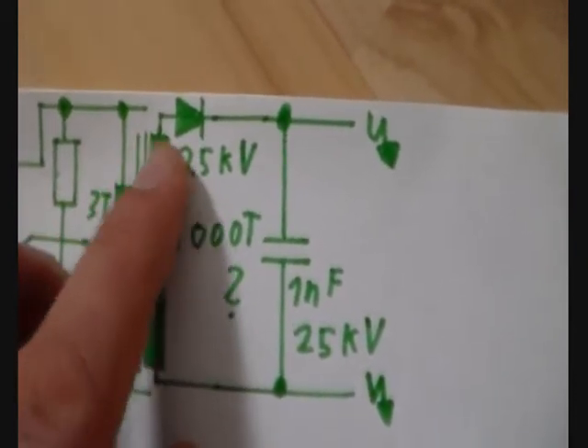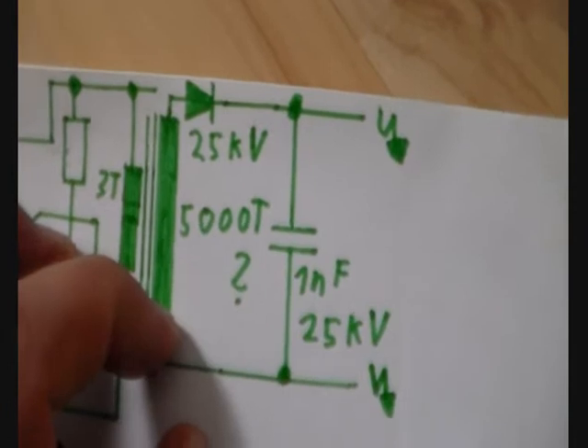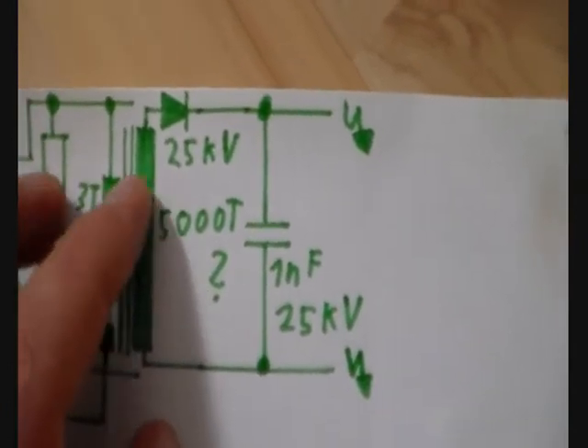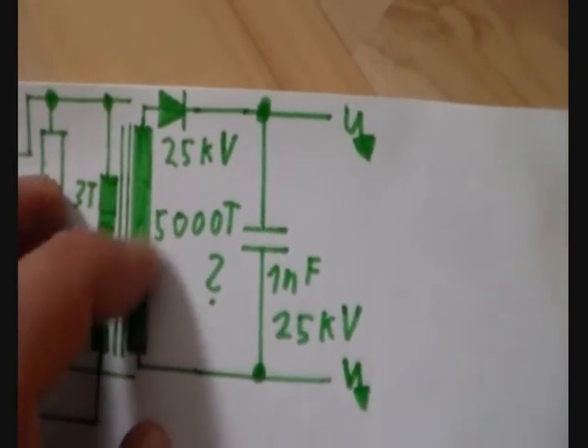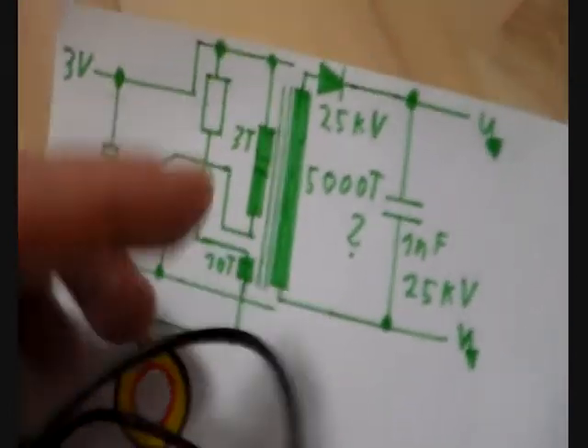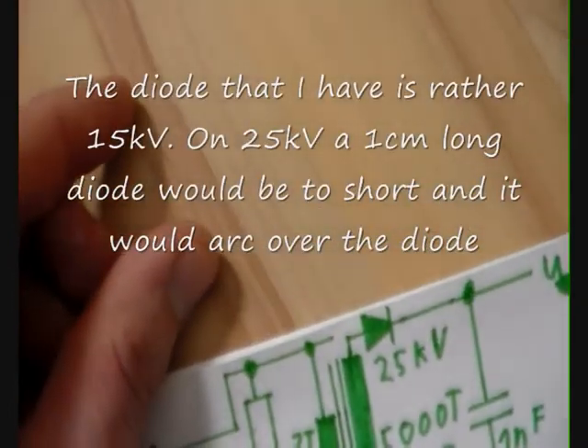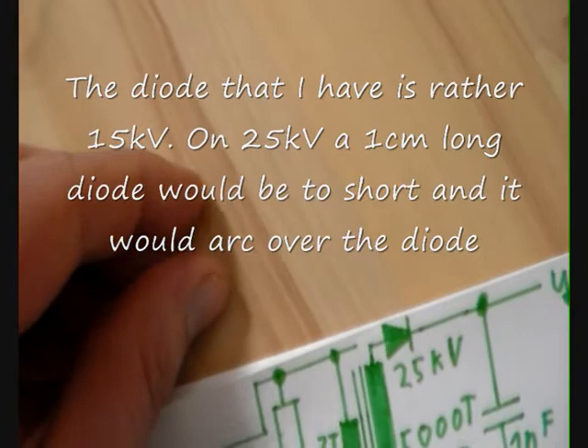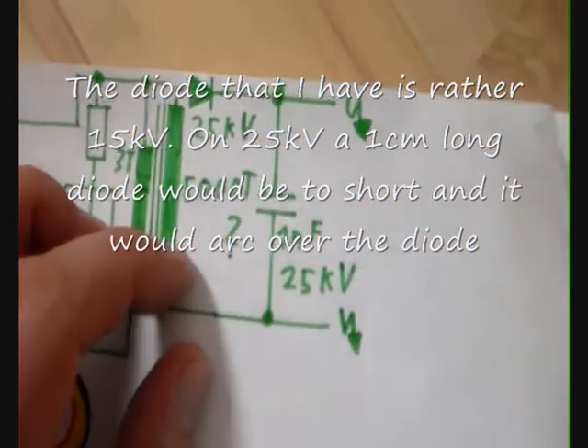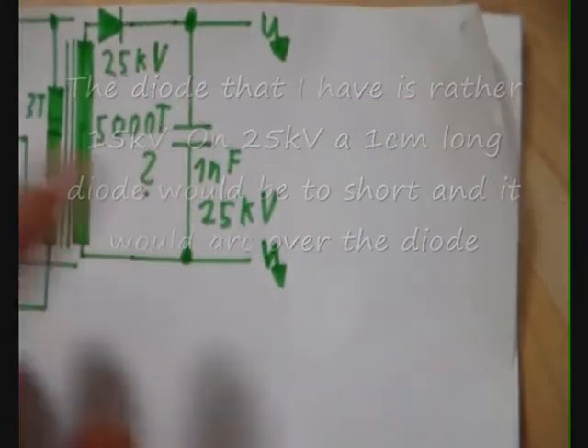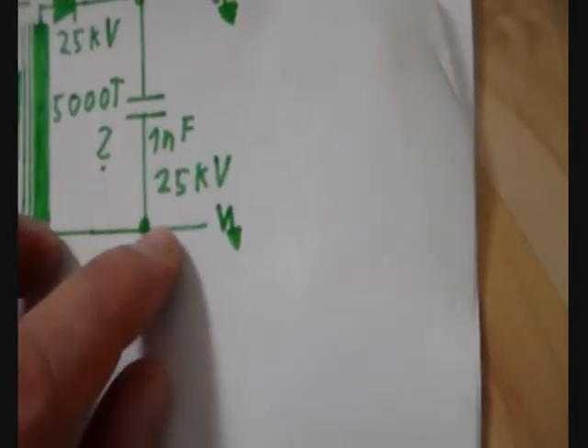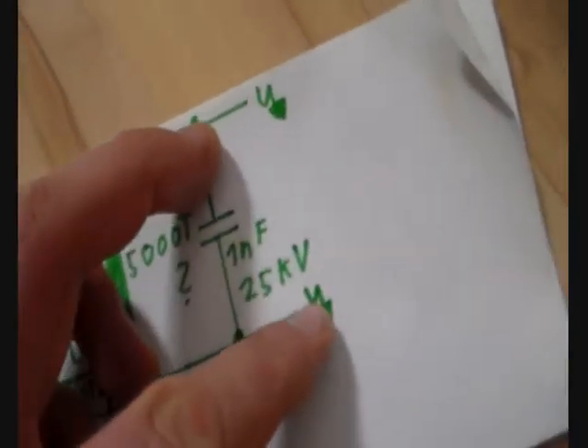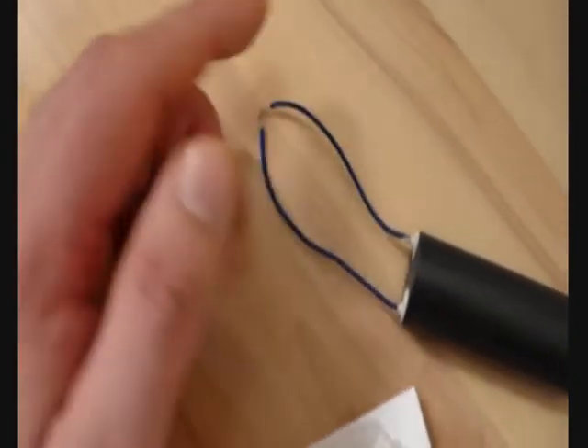Then you have a diode rated around 25 kilovolts - I've seen these around, I even have one here, about this long and this thick, a 25 kilovolt diode. Then you have a capacitor somewhere in the 1 nanofarad, 25 kilovolt range. And of course you have your high voltage output leads.